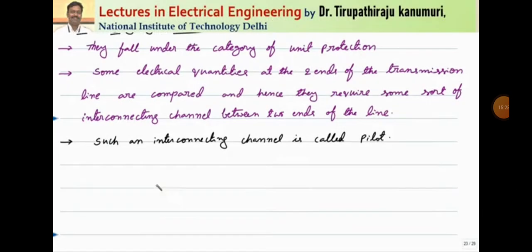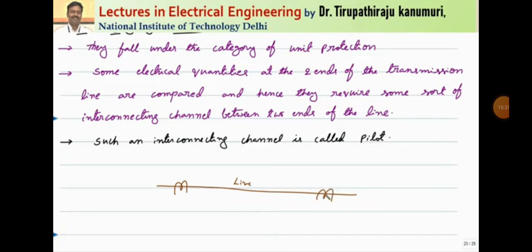In unit protection, if you are taking your transmission line, CTs are connected at both ends. The quantities at these two ends are compared and accordingly a decision is made. Whichever zone you want to protect, the CTs will be placed on both ends of that particular zone. This is the zone of protection, and the comparison of electrical quantities from both ends is used for making decisions.